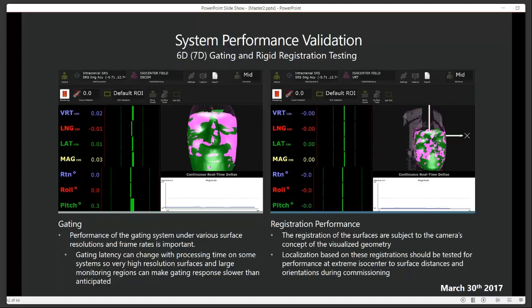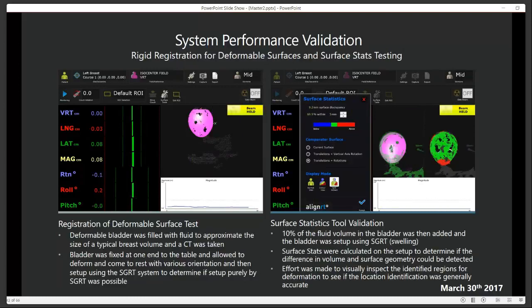Some of that might not be clinically relevant for you, but we test things almost until we can break them, is our mantra. Usually, if I can't break it, it's not done correctly. And so we try to validate your registration method against extreme conditions. In this case, rigid registration versus a deformable surface. In this case, we have a bladder full of fluid, the size of an average breast that we treat. It's allowed to fall on the table and deform in any way it wants.